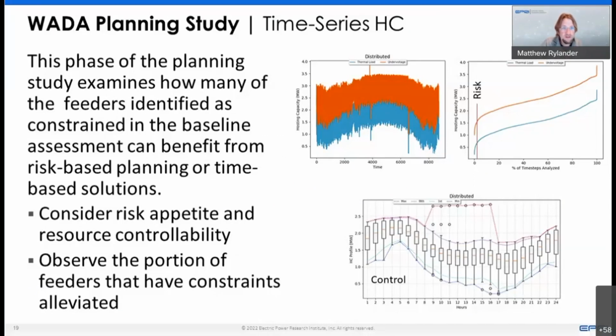That's because load and generation change operationally across the feeders during the course of the year. So there are two aspects that time-based hosting capacity gives us insight into. One is that these worst-case conditions only happen for a limited time of the year. Looking at the figures on the upper right, from a risk point of view, the worst-case scenario we sometimes plan to might be very uncommon. Fiona showed this 20% figure—that was just a random number we work towards—but it might be that the 1 to 2% of the year it represents might not actually happen. If that small percentage is excluded, our hosting capacity by itself might go up considerably.